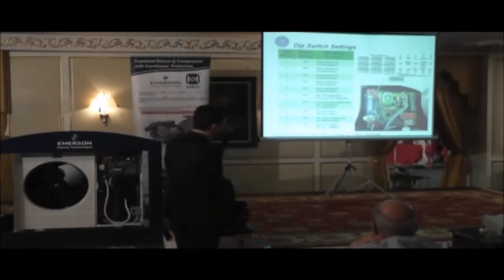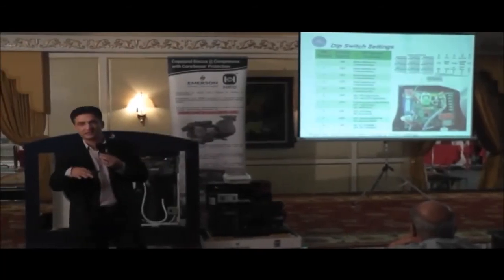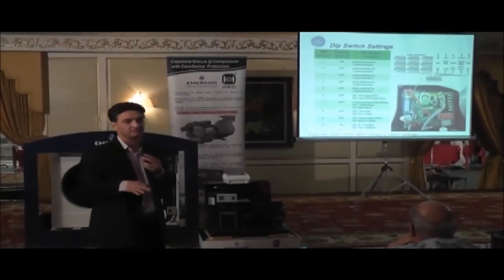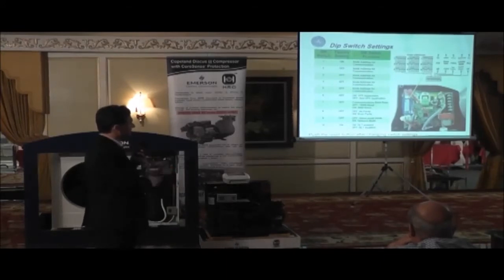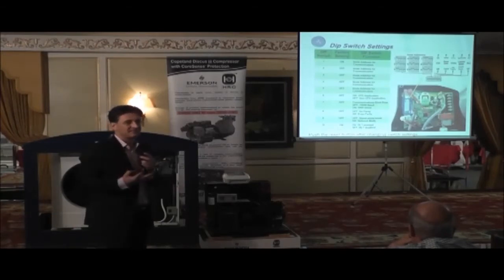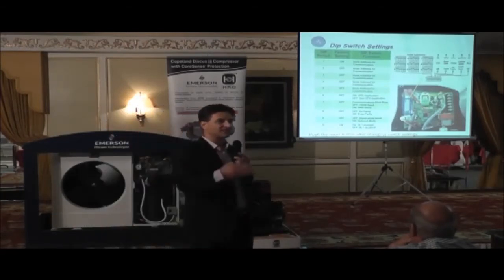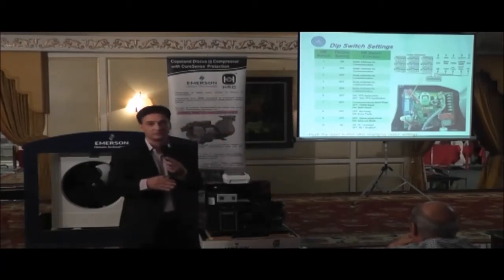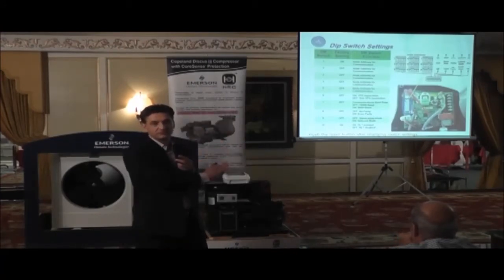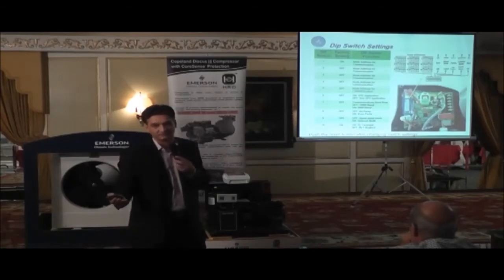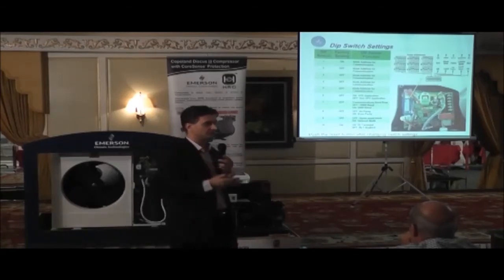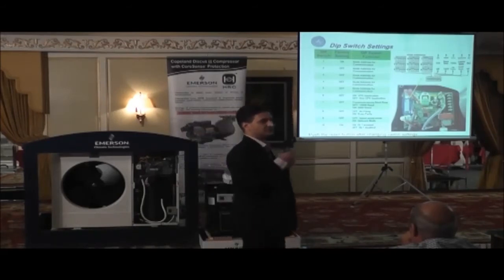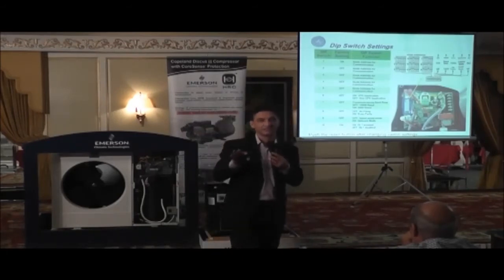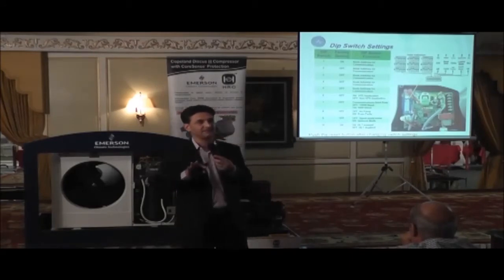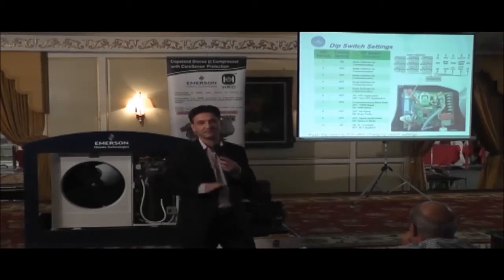Number 6. If you purchase the compressor and you're going to use a VFD on it, you need to change the setting of 6 to on for VFD application. And what we're basically doing with this, all the voltage and current protection that we've got on the motor is now going to be ignored by this module, and we're going to leave that to the VFD. Typically the VFD has got all the voltage, imbalance, low voltage, current and so on built into the VFD. So we allow the VFD to become the master in protecting the motor.